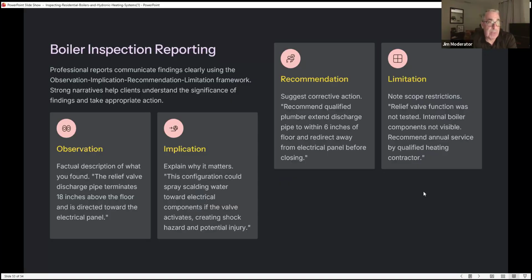Boiler inspection reporting. So again, in all our webinars, we are hitting this 4-point observation, implication, recommendation, and limitation. I have switched 90% of my report. I'm in the process of upgrading my reports to do an observation of a factual description of what you found. The relief discharge pipe terminates 18 inches above the floor and is directed towards the electrical panel.